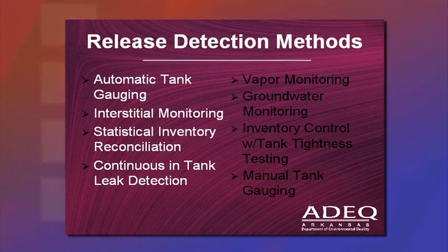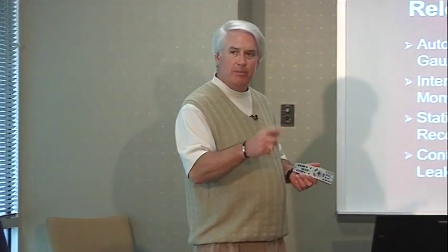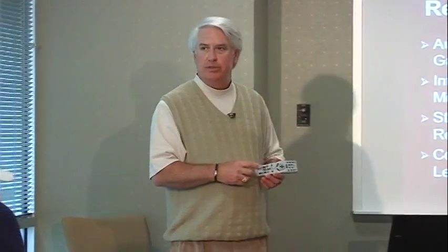Just get a visual of what you're seeing there. It doesn't matter what it is. They're going to ask you any of these. How long do you have to keep the records? You've got to keep them for 12 months. How often do you have to do these tests? You have to do these tests at least once per month. You've got to keep the last 12 months of records.